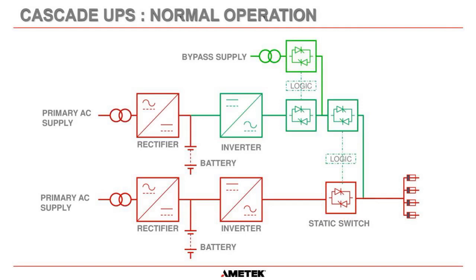The pros of a cascade system is, if you ever needed to do this, UPS A could be made by AMETEK SCI, and UPS B could be an older system that is a different manufacturer. So if you're trying to upgrade a system, you can actually have two mismatched manufacturers in a cascade system. Obviously, AMETEK SCI wouldn't recommend that. We would recommend that you have SCI UPSs for UPS A and for UPS B, but it is possible.